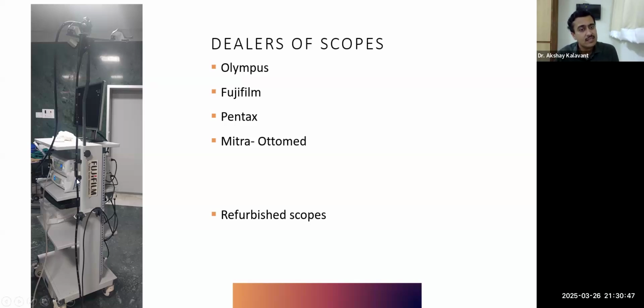Other than that, there are the light sources. Nowadays, as is happening in other instrument sections also, the life of the endoscope lights is limited, like say 480 to 500 hours. Soon after you complete say 500 hours of use, it gets switched off. Then you have to replace the light.